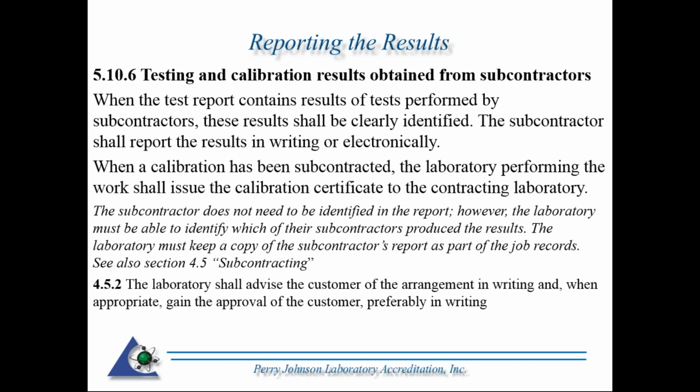Reference section 4.5, which is the actual requirements for subcontracting, where 4.5.2 specifies the laboratory shall advise the customer of the arrangements in writing when appropriate and gain the approval of the customer, preferably in writing. So that is stated earlier in the standard: prior to subcontracting any reports, the customer needs to be notified.